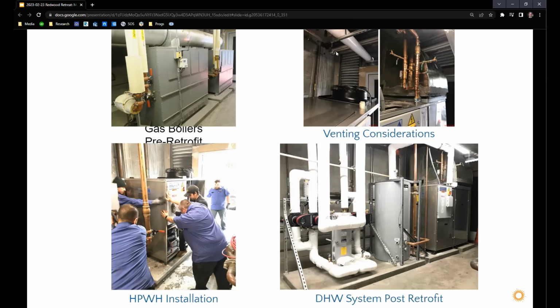So you always want to have it very close to the outside wall, but that can also bring up noise concerns. More and more units are lowering their decibel levels, which is good to see. We were able to get there with Colmac using a variable speed fan, but I know Colmac has improved their base specification, and there are more units available now with lower decibels. That's definitely something to consider on projects—what is the decibel rating of that product.